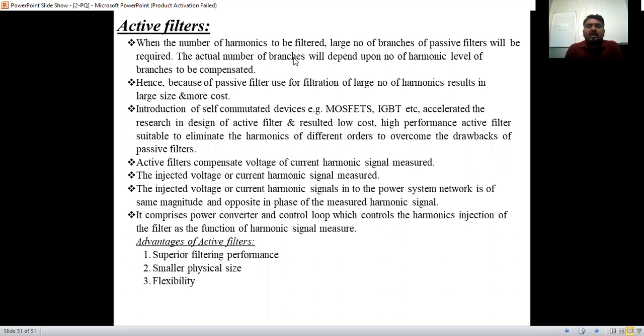So by using self-commutated devices, they have reduced the large number of branches, because these are suitable for any order of harmonics and can reduce the distortions. So instead of the multiple branches required in passive filters, by using a single active filter we can control different order harmonics.